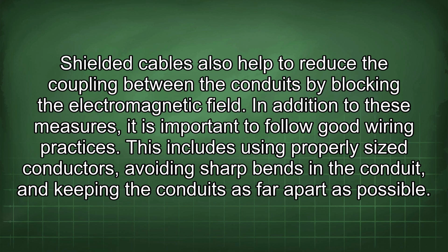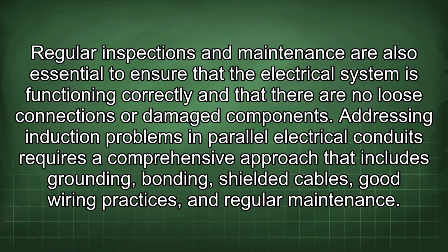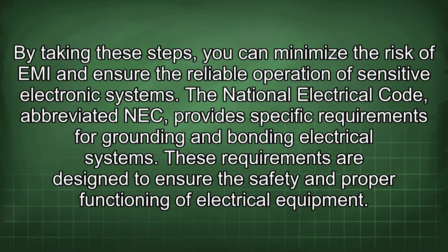In addition to these measures, it is important to follow good wiring practices. This includes using properly sized conductors, avoiding sharp bends in the conduit, and keeping the conduits as far apart as possible. Regular inspections and maintenance are also essential to ensure that the electrical system is functioning correctly and that there are no loose connections or damaged components. Addressing induction problems in parallel electrical conduits requires a comprehensive approach that includes grounding, bonding, shielded cables, good wiring practices, and regular maintenance.